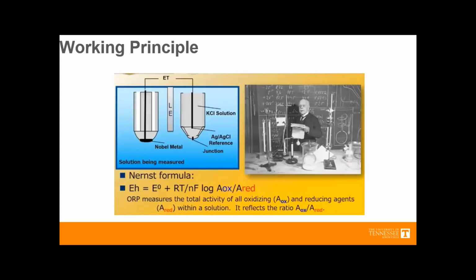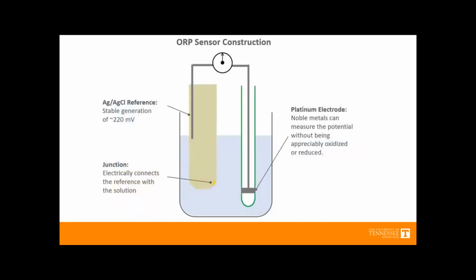If you buy a commercial probe, like this gauge meter, it's got a BNC connector. You still have two electrodes; they're just packaged a little bit differently. What I think is going to be easier for the students to do is make two separate electrodes and then kind of tie them together. So that is the Nernst equation. Something like this is what I anticipate that they would make. They have a reference where you've got your silver wire and some silver chloride, and then just something inert with your noble metal surface on the end.